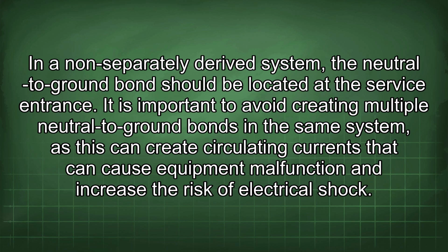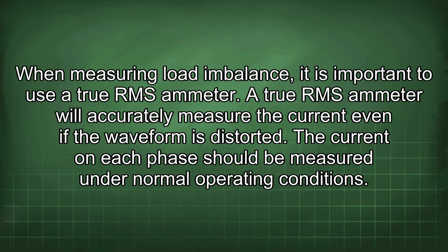It is important to avoid creating multiple neutral to ground bonds in the same system, as this can create circulating currents that can cause equipment malfunction and increase the risk of electrical shock. When measuring load imbalance, it is important to use a true RMS ammeter. A true RMS ammeter will accurately measure the current even if the waveform is distorted.